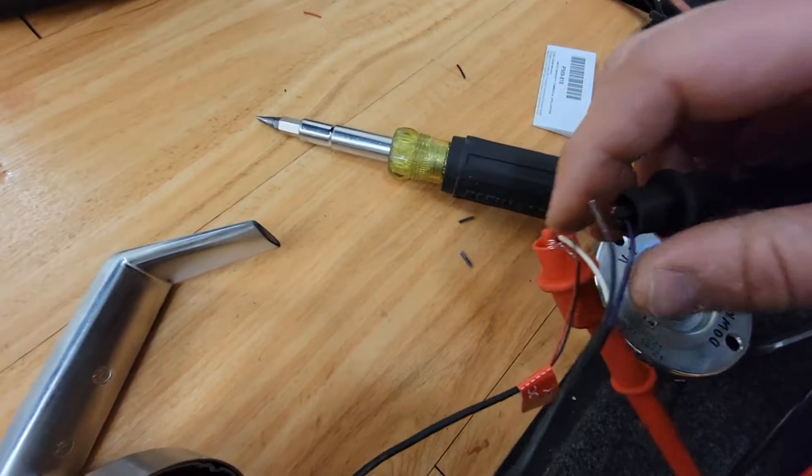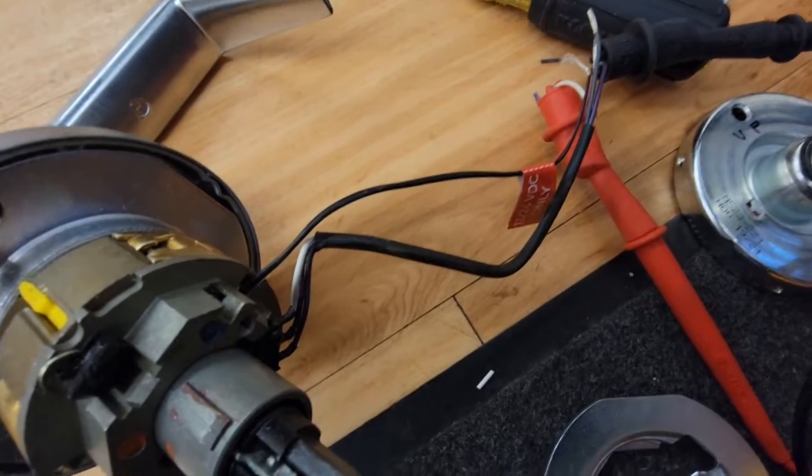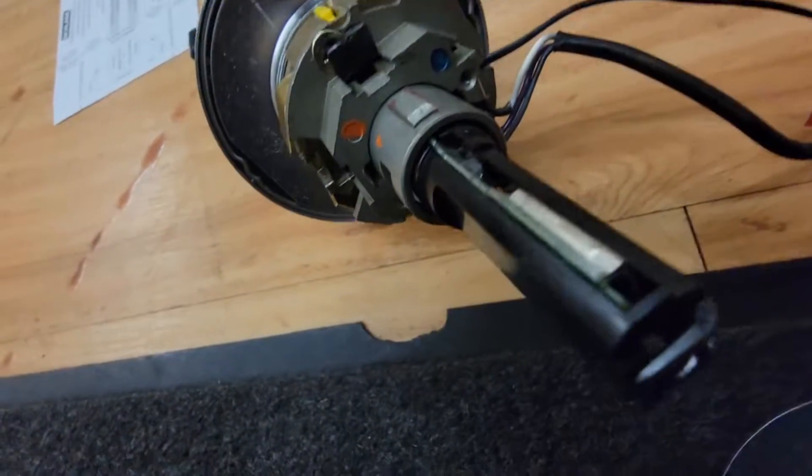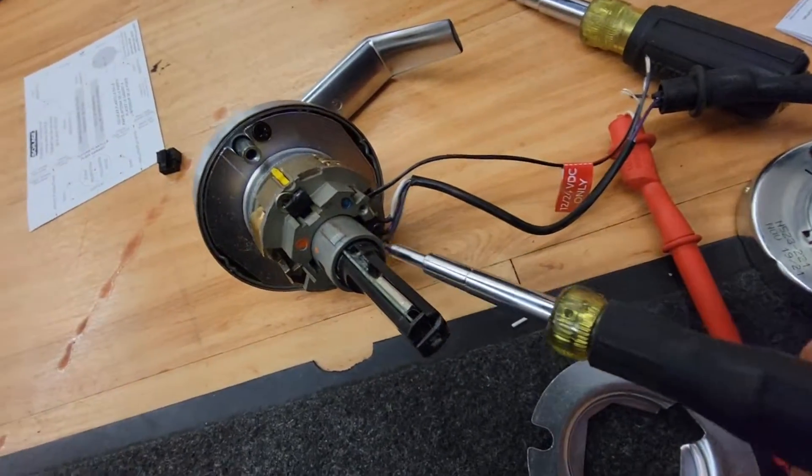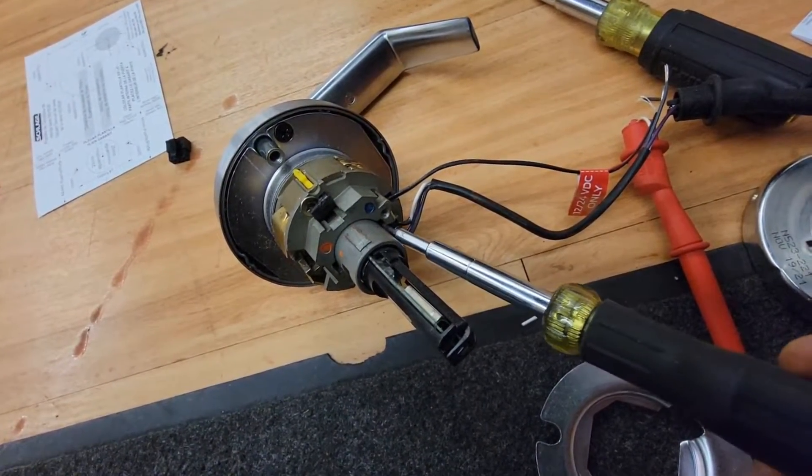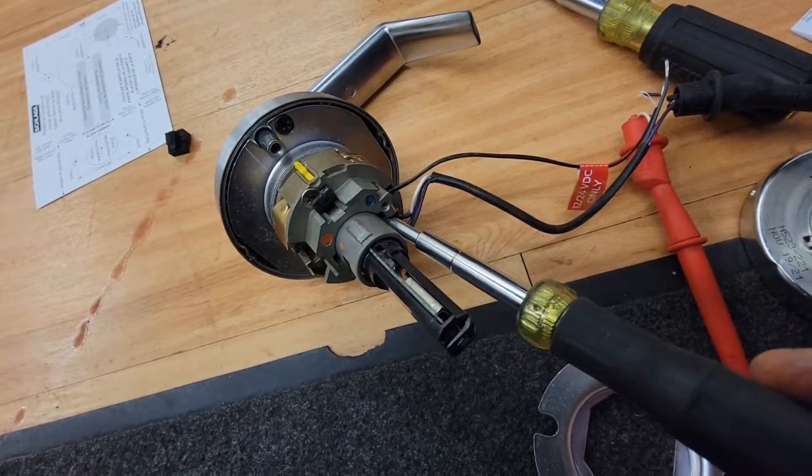I knew the white was the common. Just to test this, I'm setting my meter on continuity. This little micro switch right here - that's our request to exit - so I am on normally open.